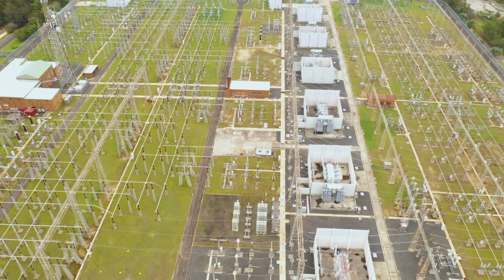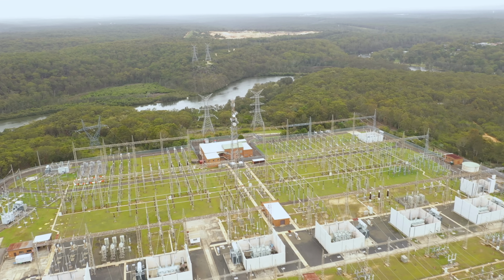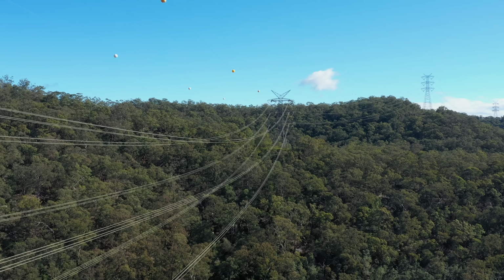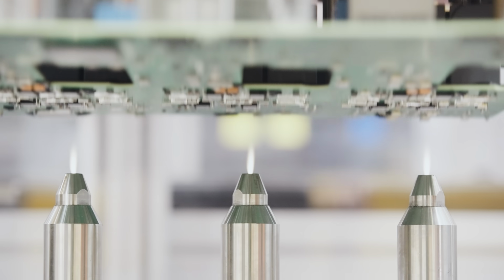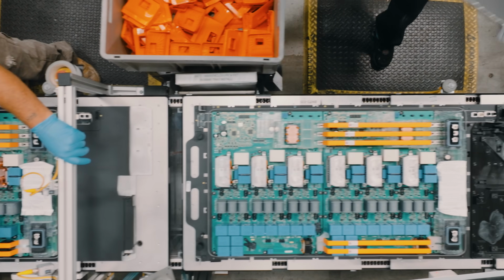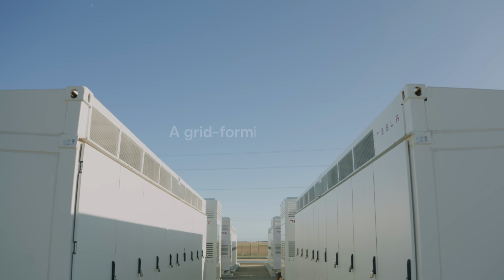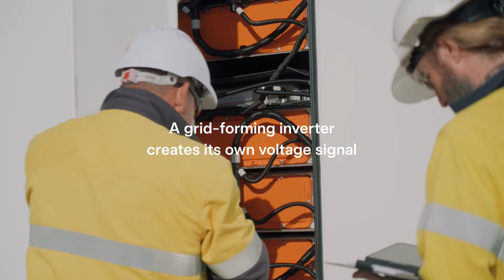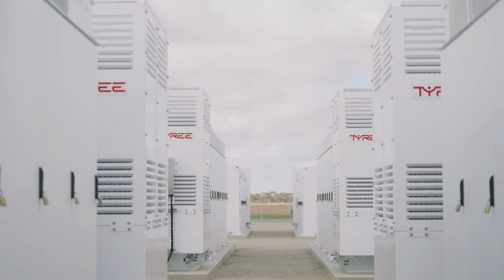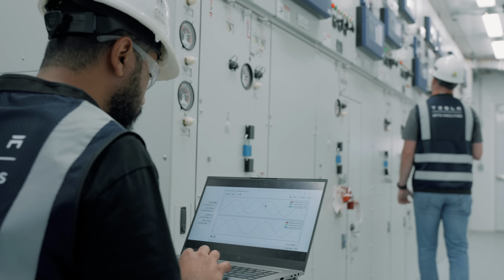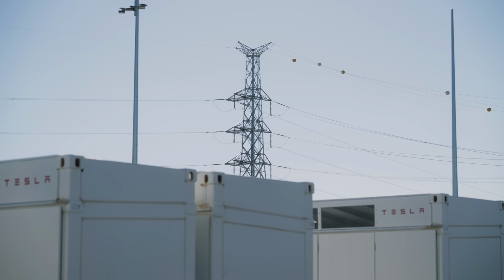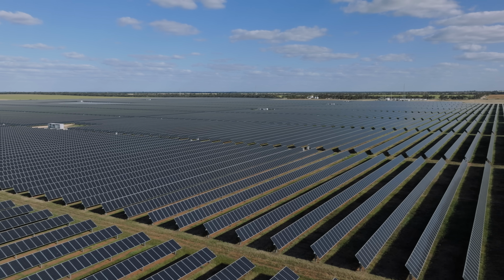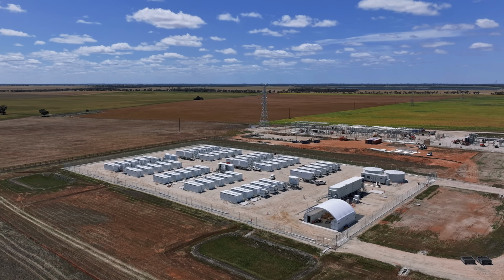Weak grids can struggle to stay stable, making it harder to connect renewable generators that rely on a steady voltage. Tesla's Megapack uses grid-forming inverters, which generate their own voltage signal, allowing them to operate independently of the voltage on the network. This strong voltage signal restores and maintains grid stability, which supports the connection of more renewable energy into that part of the network.